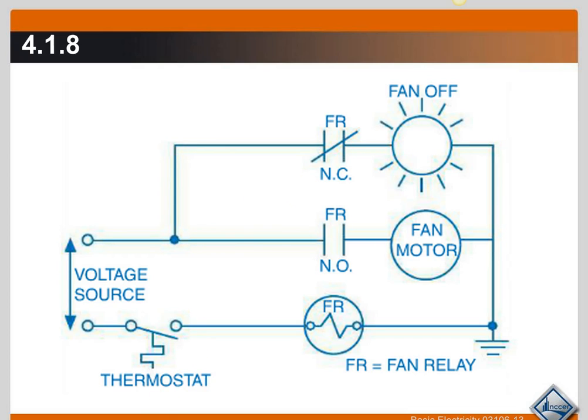Now we have our temperature controlled switch which is the thermostat. This is going to close on temperature rise. Remember the bi-metal strip here, this heats up and it expands and it's going to close this switch. Every schematic diagram you're going to have to do this in your head.